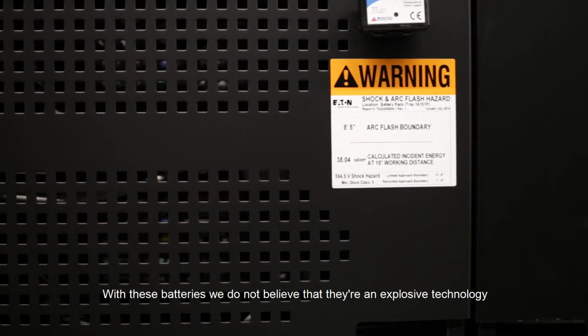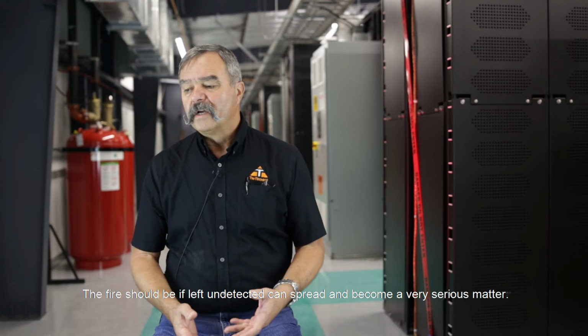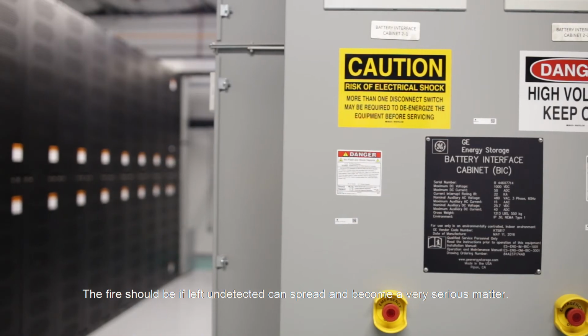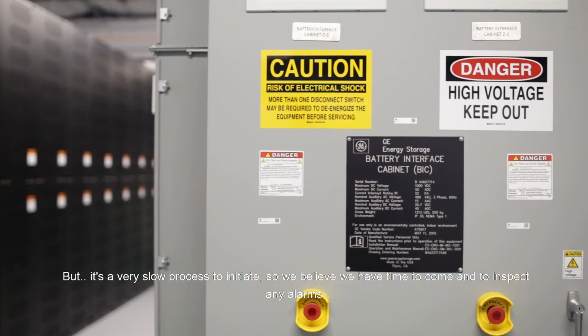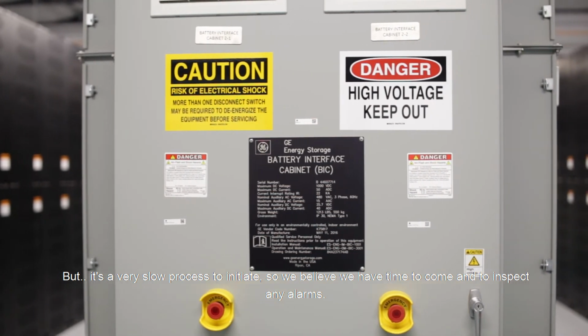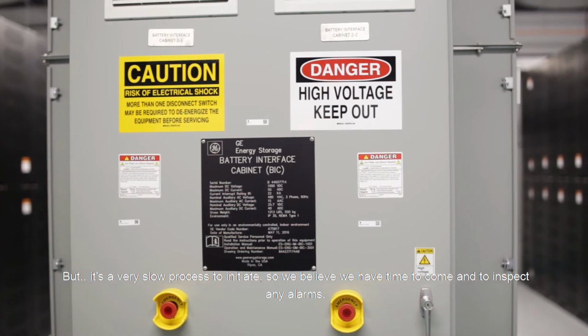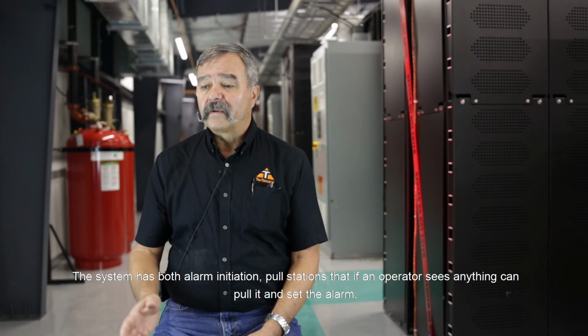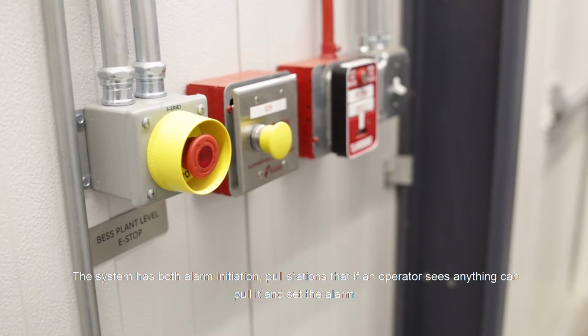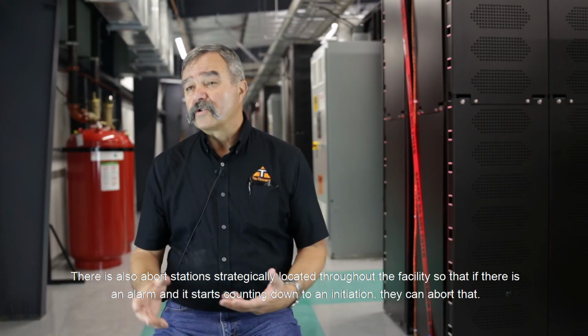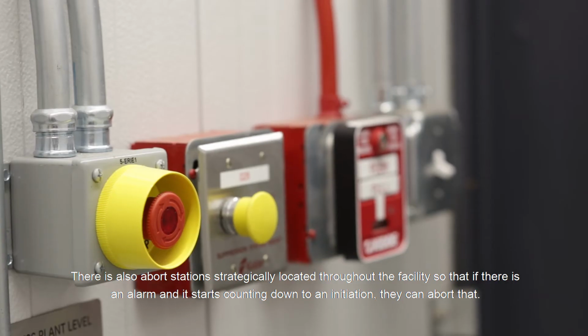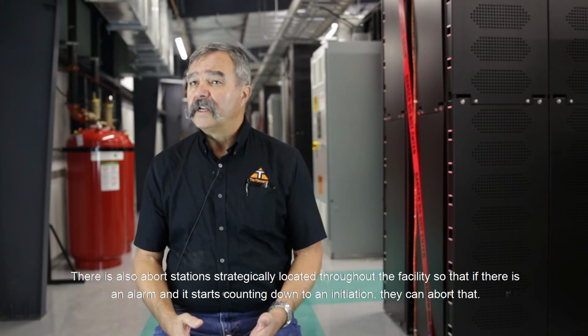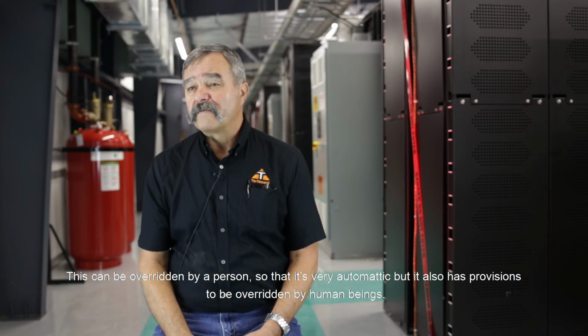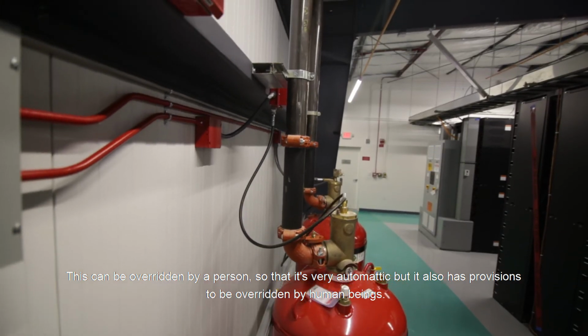With these batteries, we do not believe that they're an explosive technology. The fire, if left undetected, can spread and become a very serious matter, but it's a very slow process to initiate, and so we believe we have time to come and inspect any alarms. The system has alarm initiation pull stations, so if an operator sees anything, they can pull it and set the alarm. There are also abort stations strategically located throughout the facility, so that if there is an alarm and it starts counting down to an initiation, they can abort that. It's very automatic, but it also has provisions to be overridden by human beings.